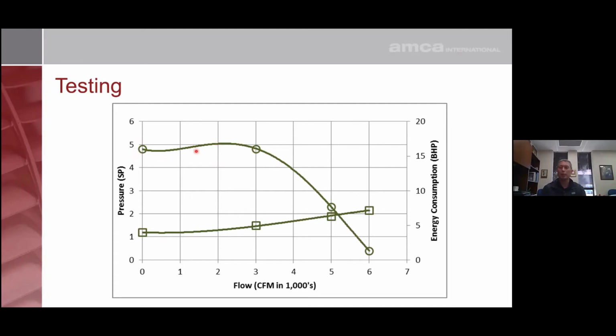And you can use a cubic spline, you can use a polynomial least squared. Most, and correct me if I'm wrong, Lisa, most fan manufacturers use AMCA's curve interpolation program to interpolate between the points. And it'll produce something that's a little bit tighter fitting than a polynomial least squared curve fit program. Going back probably 25 years ago, we tried to experiment with using a polynomial least squared fit program, and it produced a smoother curve and missed points more so than what AMCA's program uses. But AMCA has a specific curve fit program that's relatively accurate.